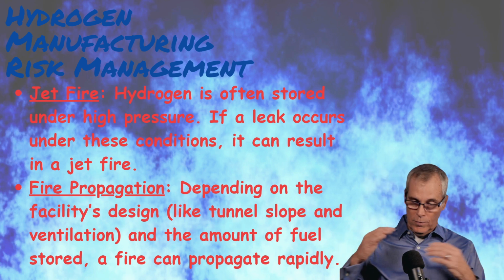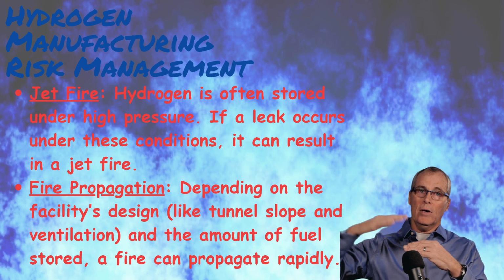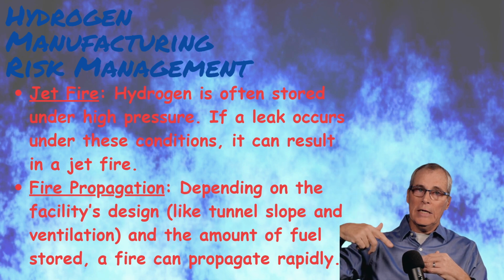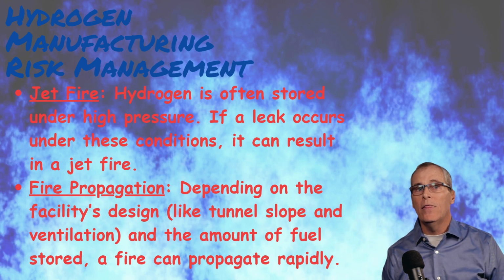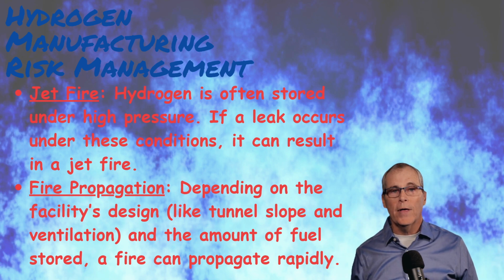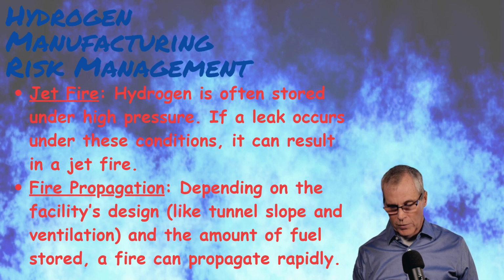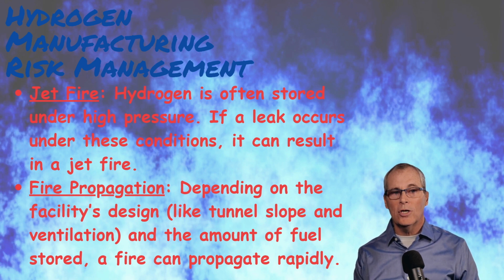If you put them out, but remember, the flame isn't even down along the metal. The flame is out away from the leak. So it may not take much to put that fire out, and then you have to deal with that cloud of gas. So be very careful about dealing with jet fires.